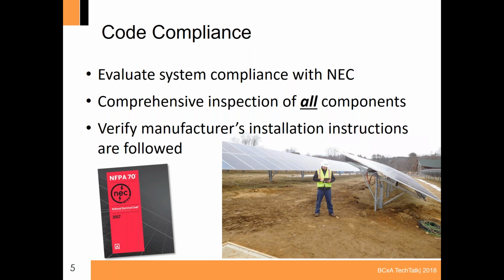Like I said, we want to inspect all of the components. We also read a lot of installation instructions, probably more than I would like to admit, but to really understand how something is installed, it's so important to fully know the instructions front and back, make sure they're followed. So the code itself, the electrical code, contains many articles that are relative to PV installations. There's two sections dedicated to solar PV per se, but there's also several other articles that would apply. So we try to make sure we are aware of all of these articles and that we cite the appropriate articles if we do see issues.